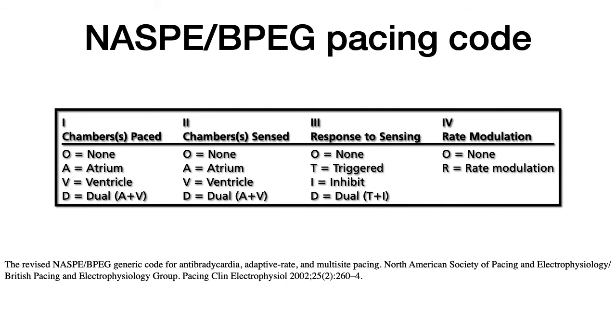The pacemakers are classified by the nature of their pacing mode. The classification follows the code that was developed by the North American Society of Pacing and Electrophysiology and the British Pacing and Electrophysiology Group. This code was last revised in 2002. Most pacemakers are programmed to inhibit pacing when they sense the native electric activity and to pace in the absence of this electrical activity. They can be programmed to set which chamber will pace and which chamber will sense the intrinsic activity, how the pacemaker will respond to the sensed electrical activity, and whether rate-responsive pacing will be used or not. This code describes the pacemaker modes.